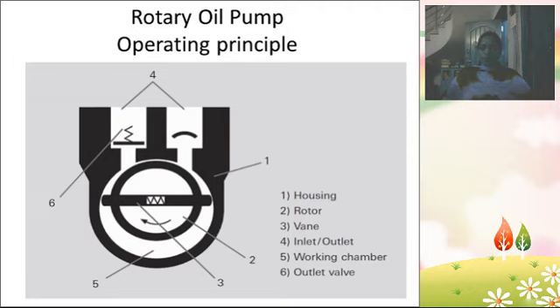It consists of an outer cylinder with a rotating cylinder rotor. The rotor R rotates eccentrically inside the outer cylinder with the help of an electric motor. Here C is the inlet tube which is connected to the vessel to be vacated, and O is the outlet valve. The pump is immersed in oil to avoid leakage.